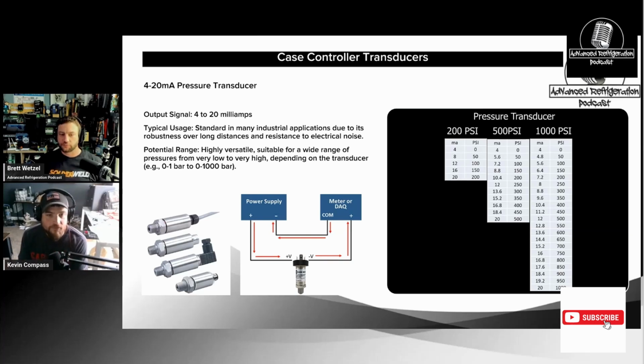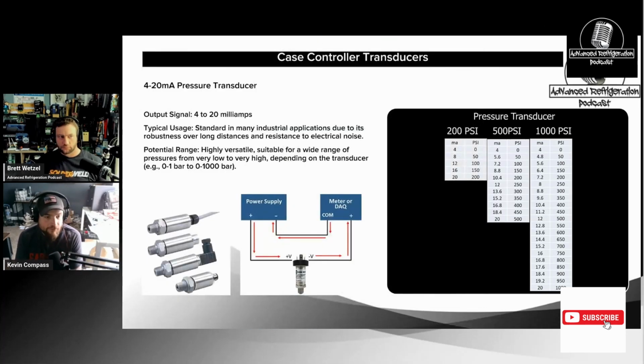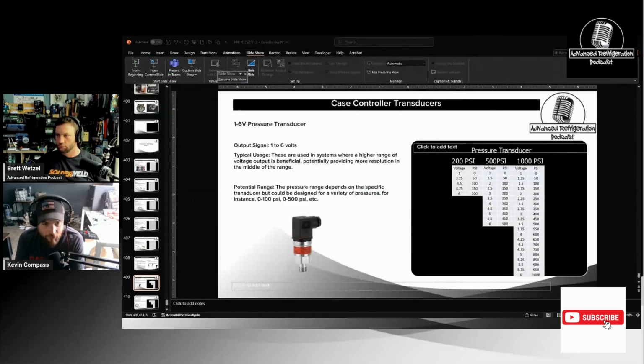Go ahead, keep talking. So standard 4 to 20 milliamps, you're going to have a power supply. You could have a master power supply for the rack supplying everything that's 4 to 20 milliamps in here, so all your transducers can come off of it. The way it's going to work is you're going to have a positive wire on the transducer going from the power supply. The negative of the power supply has to be tied to the negative of the board.